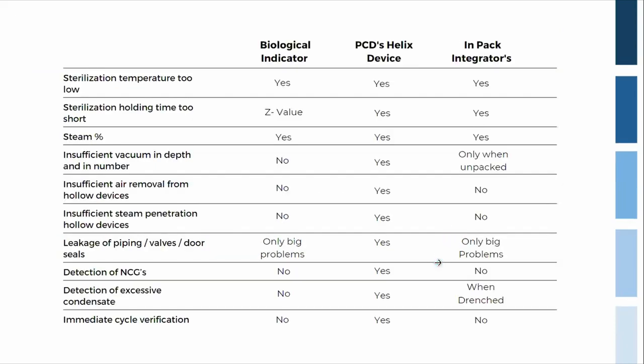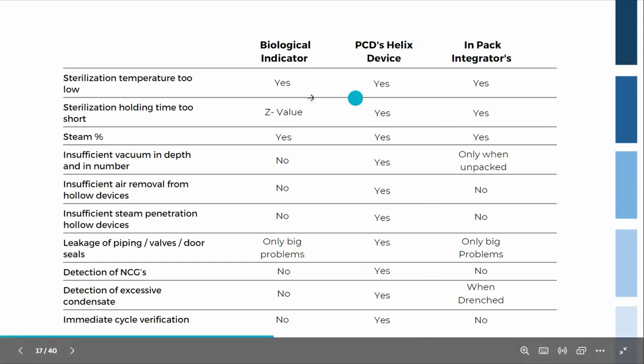Ideally, a hospital should validate all loads and combinations of loads, although this is not practical as the combination of loads varies every cycle. The most difficult to sterilize object, by means of a helix, is not only advised to be used as a Bowie-Dick test pack, but also as a cycle monitoring device. So here you can see why we refer to it as the most difficult one. It tests most of your parameters.